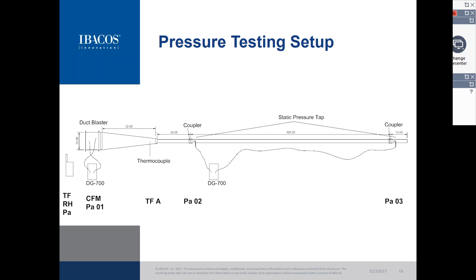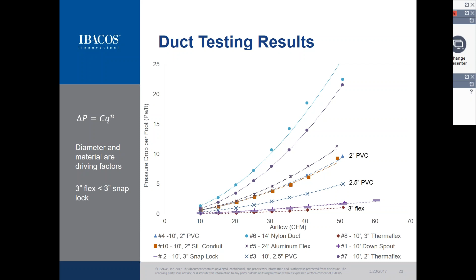Some simple results here: as you'd imagine, diameter is the biggest driving factor. We plotted the pressure drop per foot for various duct materials. It's a lot of data, and I don't expect you to process all of it, but you can see the 2.5-inch PVC pipe fits somewhere between the 2-inch PVC and the 3-inch flex duct. These were the three materials we primarily considered. 2-inch PVC is probably a bit too small for conventional homes, but we think there's a lot of potential with something between that 2.5-inch PVC and the 3-inch flex duct.